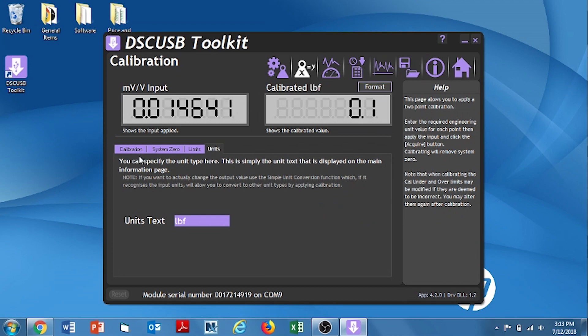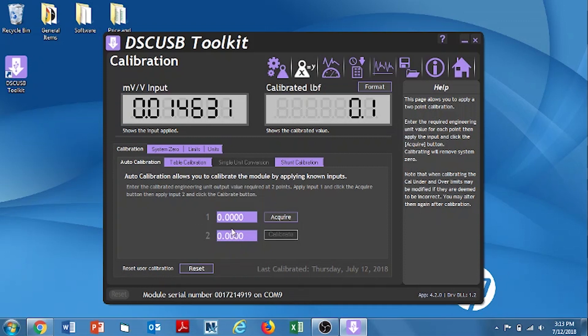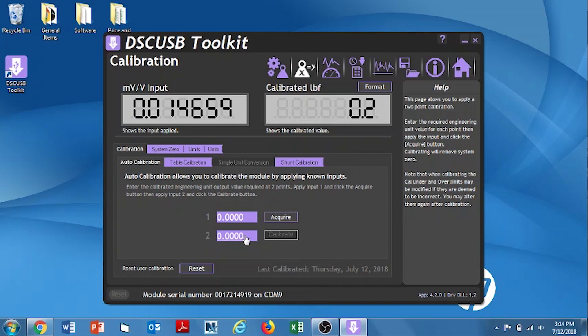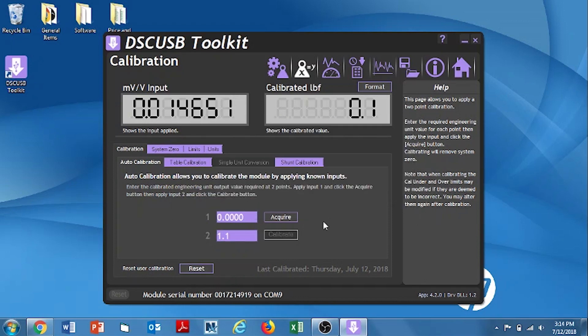Next, we're going to actually perform the calibration. This will be a two point cal. So, we're going to hit this button called calibration. And then, make sure we're on the tab that says Auto Cal. Our first point will be 0. Which we'll acquire with no load on the load cell. And our second point will be, and we're going to type that in right now, as I stated before, 1.1 pounds. Once I click OK, it's ready now to do the live cal.